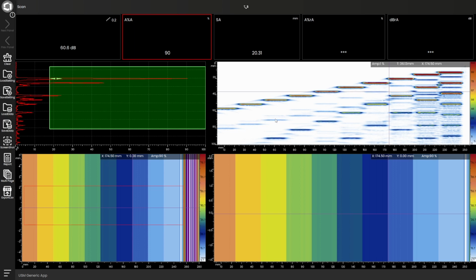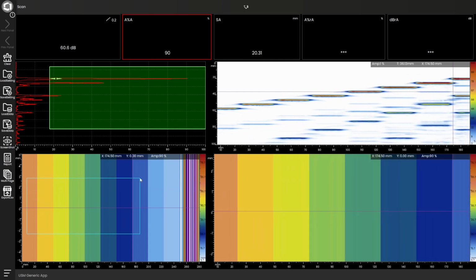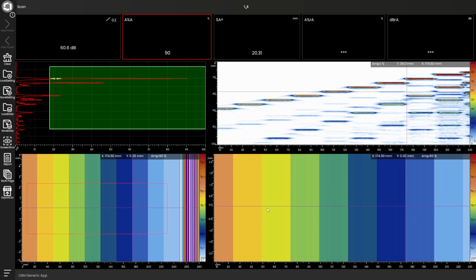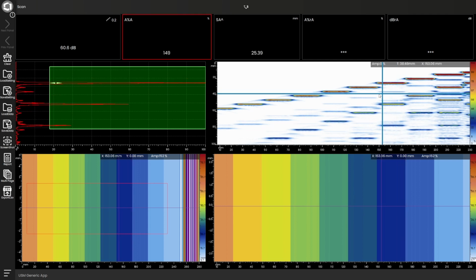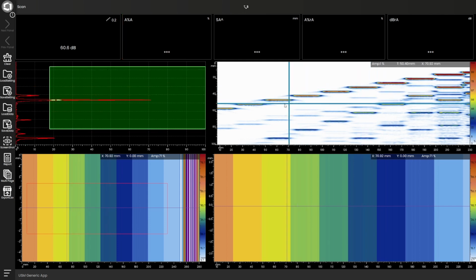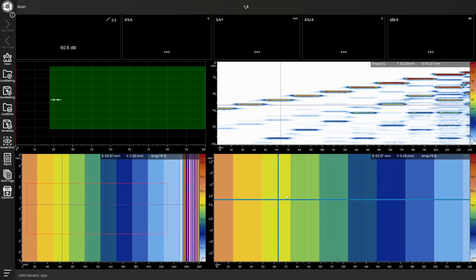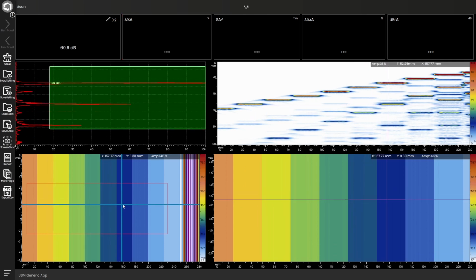In the upper left corner is the A scan, upper right corner is the B scan, lower left is the overview C-scan, and lower right is the active C-scan. So if I put a measurement box down on the overview, that selects what appears in the active window and the B-scan window. So the B-scan and active window align vertically, and the B-scan aligns with the A-scan vertically. So wherever I place a measurement cursor on the C-scan or the active B-scan or over here on the overview, the point directly under that cursor is going to be what appears on the A-scan. So these views all sync together.